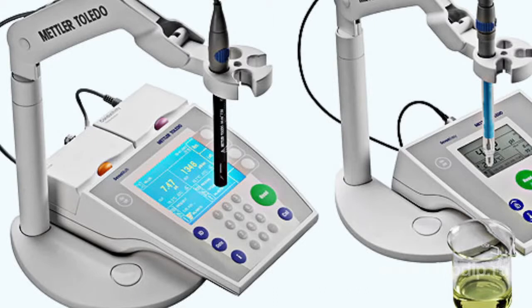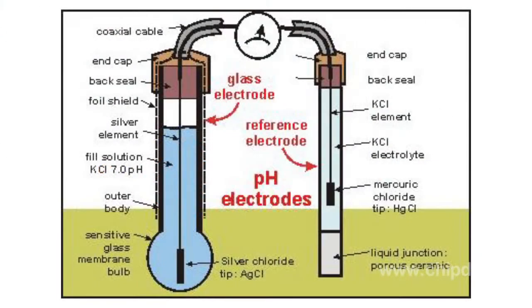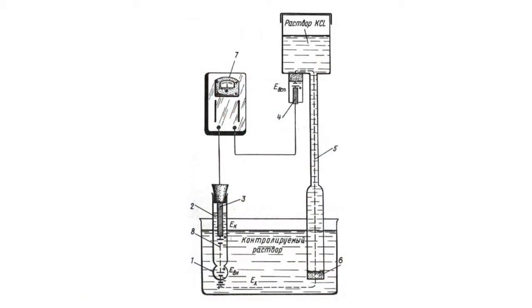The pH value of a solution can be accurately measured with the help of a pH meter, which is in fact a kind of potentiometer. A pH meter is based on measuring the EMF of a galvanic cell consisting of a glass electrode with a potential depending on the pH, and a comparison electrode, both placed into the solution being tested. The EMF of the system is registered with the help of a millivolt meter.